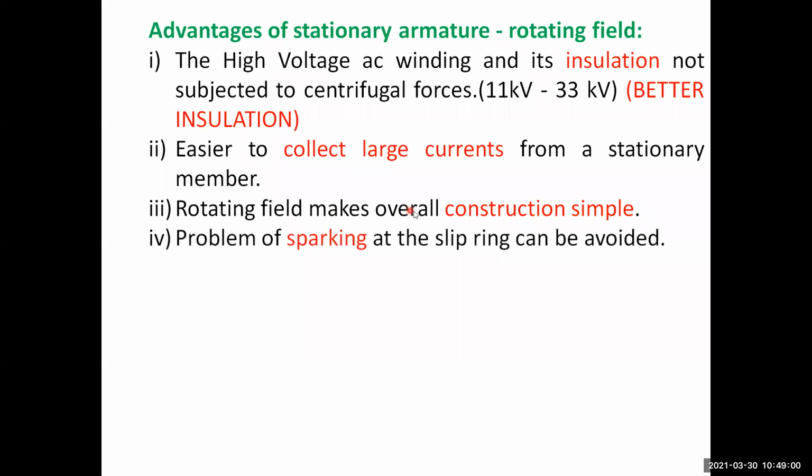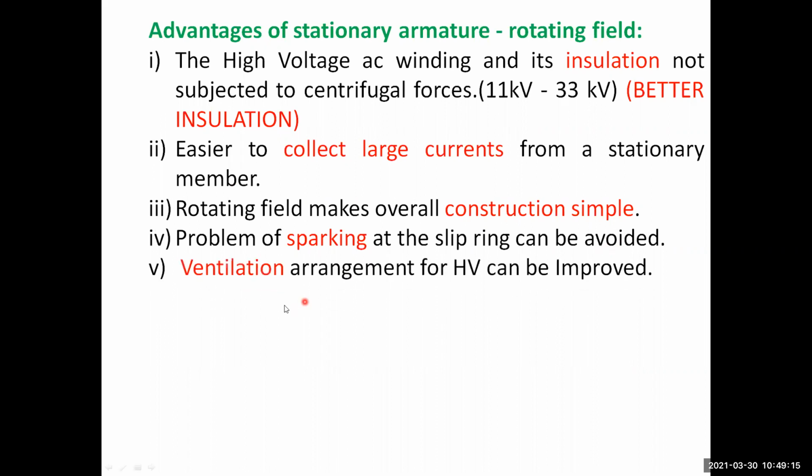A rotating field makes the overall construction simple. The problem of sparking at the slip rings can be avoided, since the sparking across the brushes is avoided. The ventilation arrangement for high voltage can be improved because the stator winding is stationary. So that's why the ventilation arrangement for high voltage can be improved.